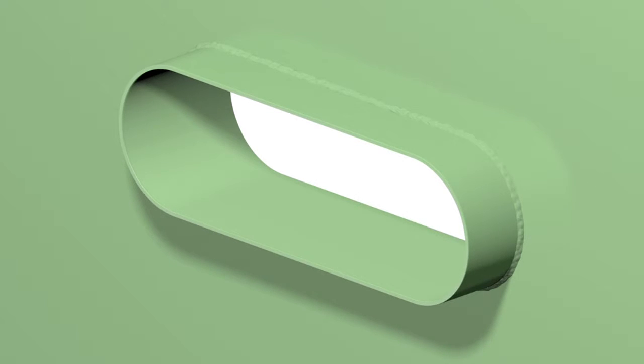Besides that, any dirt, oil, grease or other residues should be removed from the inside of the transit frame. Keep in mind that a space of 20 mm at the front and the back should remain for applying the FIWA sealant. Therefore, the sleeves are 40 mm shorter than the depth of the transit.